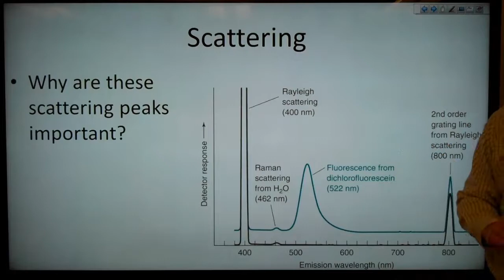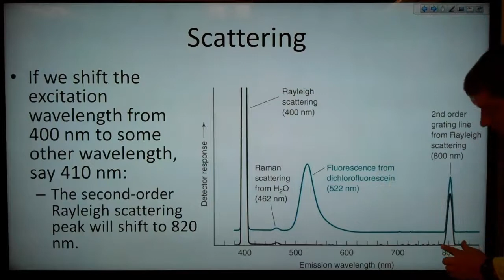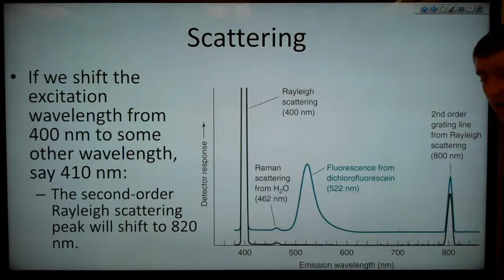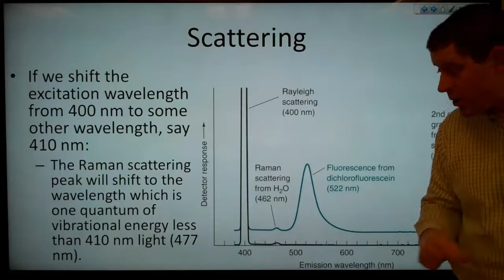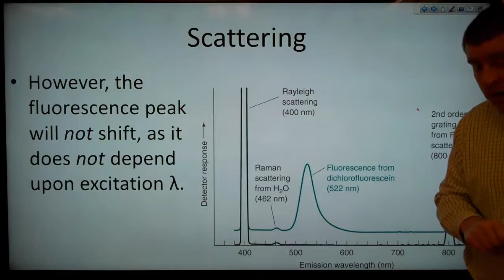So why are these scattering peaks important? Well, if we shift the excitation wavelength from 400 nanometers to some other wavelength, let's say 410 nanometers, that first order Rayleigh scattering will shift to 410 nanometers. That second order Rayleigh scattering peak over here will shift to 820, because it's got to be double the excitation wavelength. That Raman scattering peak will shift to the wavelength which is one quantum of vibrational energy less than 410 nanometer light, which would then be 477 nanometers. But our fluorescence peak will not shift, because it doesn't depend upon the excitation wavelength.